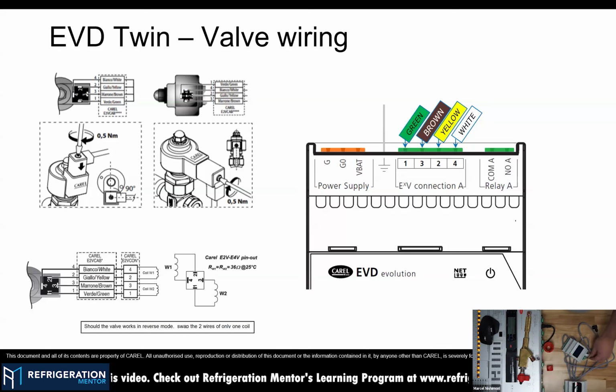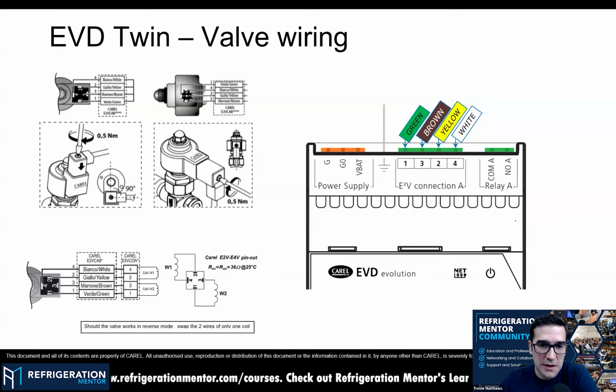And so make sure that you have the right sequence of colors. If you need to splice the wire, make sure that you are following the right sequence of colors. It's mandatory to have a smooth commissioning or startup of the system. And that goes for any electronic valve. You've got to have the right wires on the right winding.